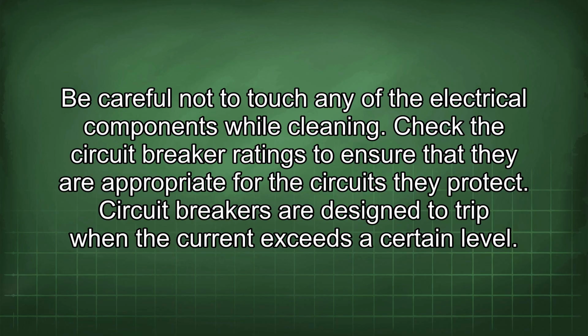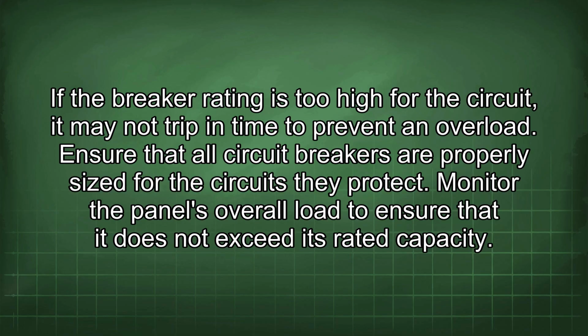Check the circuit breaker ratings to ensure that they are appropriate for the circuits they protect. Circuit breakers are designed to trip when the current exceeds a certain level. If the breaker rating is too high for the circuit, it may not trip in time to prevent an overload. Ensure that all circuit breakers are properly sized for the circuits they protect.